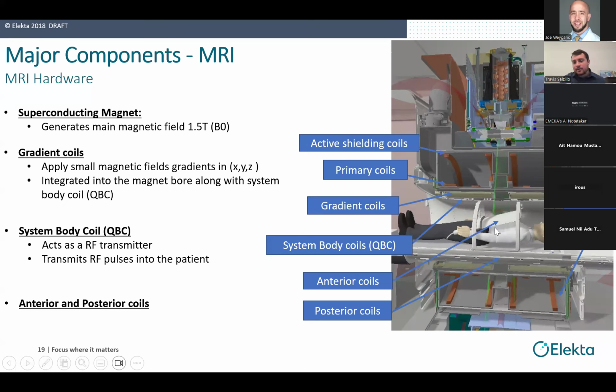I will say that personally working with these, this is really where I think the high yield impacts would be. If we could get better coils, that's my wish list when it comes to these systems. You have such a high magnetic field, but you lose a lot of your SNR because the coils are of a surface coil based approach, which are non-conformal to the body. They exist within this circular apparatus that you can lower towards the patient, but it's not like the flex coils that you might see in a Siemens system, for example. So there's a lot of opportunity space for coil development for this system. One thing about this coil is it is radiolucent, so you can shoot through it. You don't have to worry about avoiding the coil whenever you're trying to plan your fields for treatment.